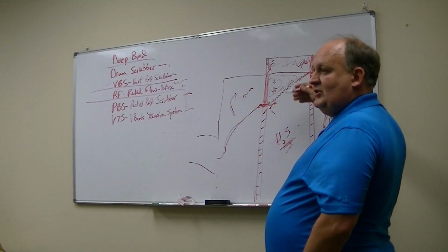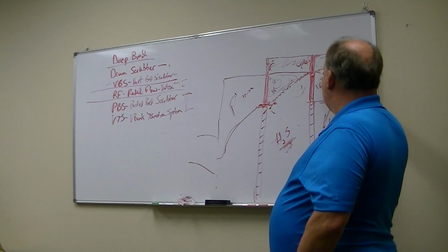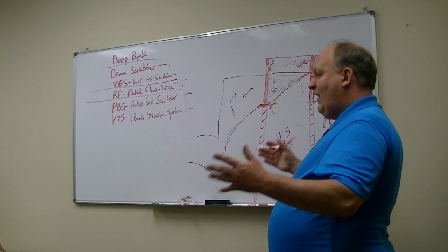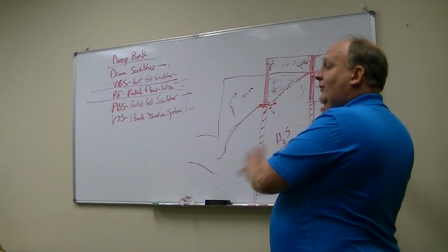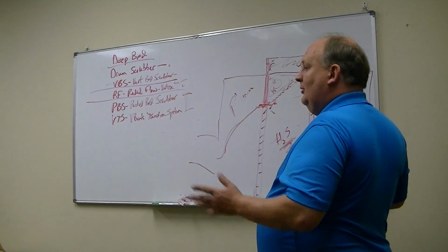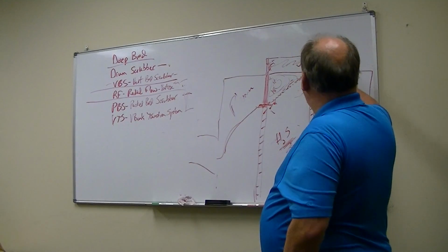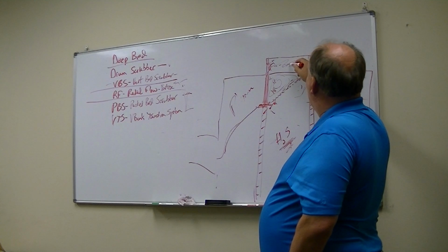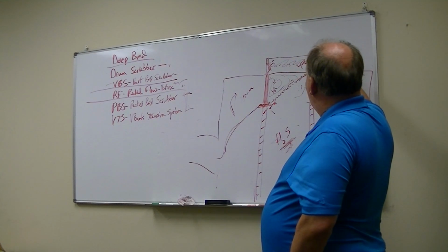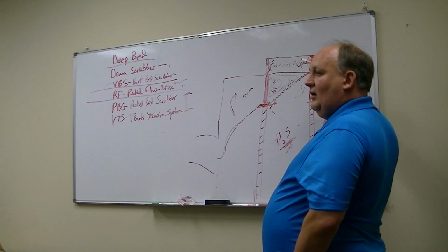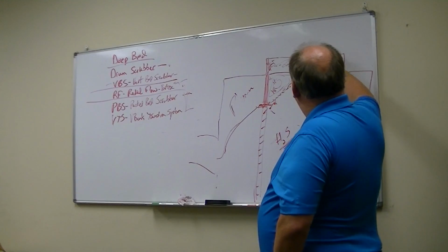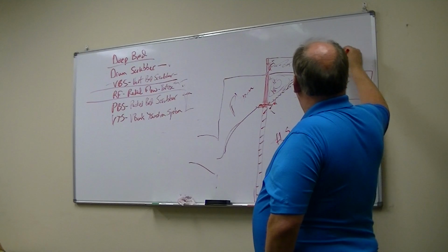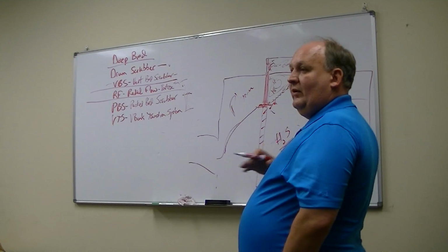And why doesn't this competitor know about this? Because they're fiberglass guys, they're not airflow guys. They make a beautiful fiberglass system, but they don't know how to operate it. They didn't even know, and really, even if their Fill-Chute was filled up all the way here, it probably would have prevented the problem as well. But certainly having a baffle and filling the Fill-Chute all the way to the top would have completely taken out the problem.